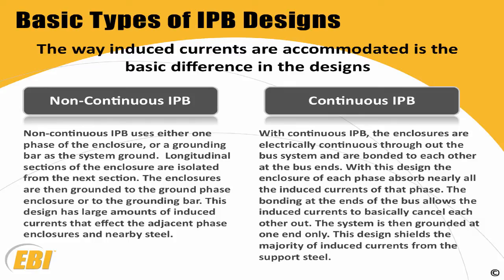Basically, you have two different types of isolated phase bus designs. The original design is what we call a non-continuous IPB. They came up with a new design, which is a continuous IPB, because of the induced currents that are emitted by the non-continuous IPB design. A non-continuous IPB uses either one phase of the enclosure or a grounding bar as the system ground. The longitudinal sections of the enclosure are isolated from the next section. Then all three of the sections are grounded across to the phase, the ground bar. This design has large amounts of induced currents that affect the adjacent phase, and also it affects the nearby steel.